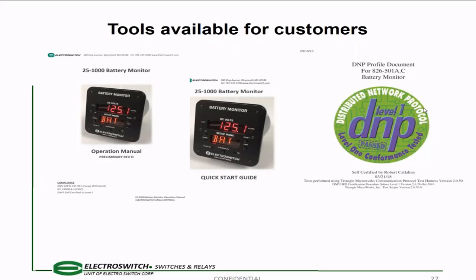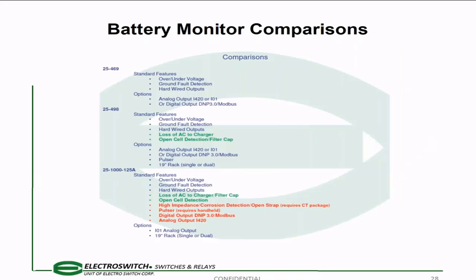And then you have the DNP profile. If they're going to use DNP or Modbus, not 4-20, this will help them as far as setting up the DNP points through an RS-485 interface. So we used to, on our old meters, 25-469, you could have standard features, high, low voltage, ground fault detection with hardwired outputs. You could have options of 4-20 or 0-1, or you could get another one with digital, the DNP 3.0 or Modbus.